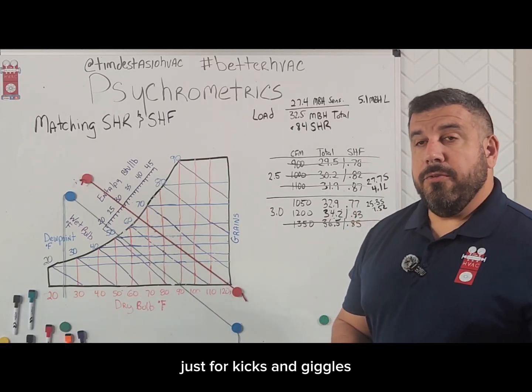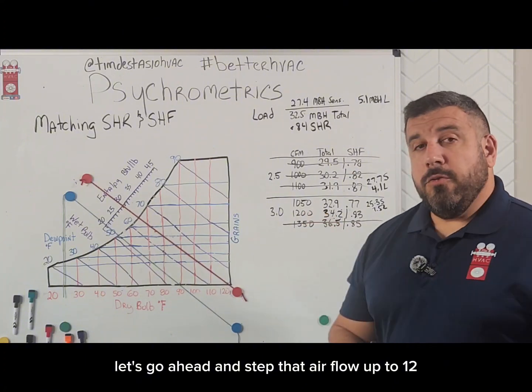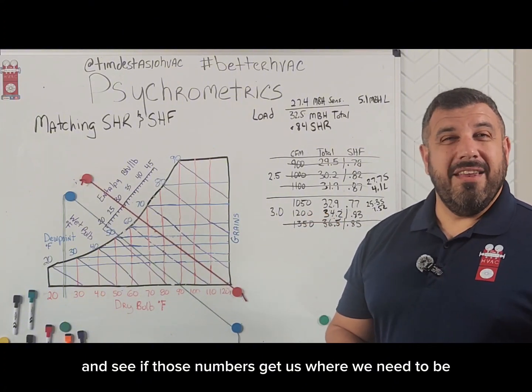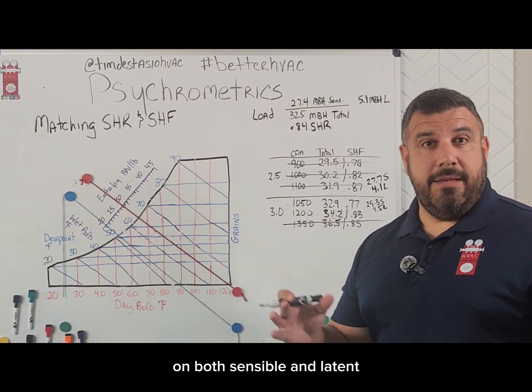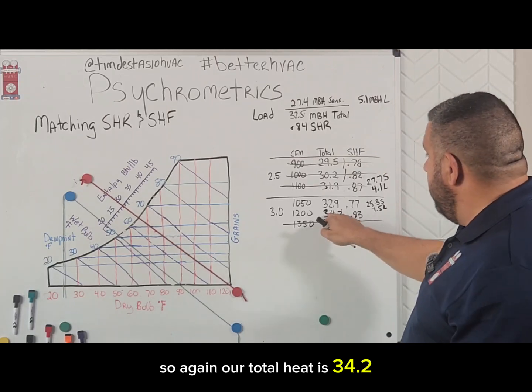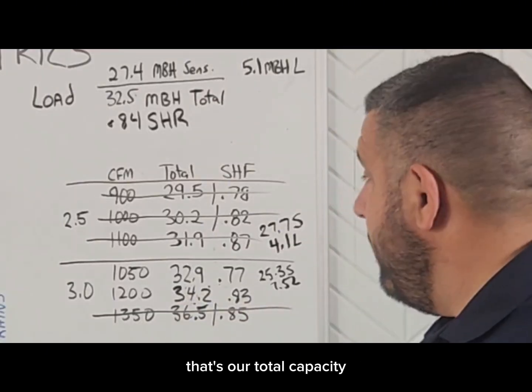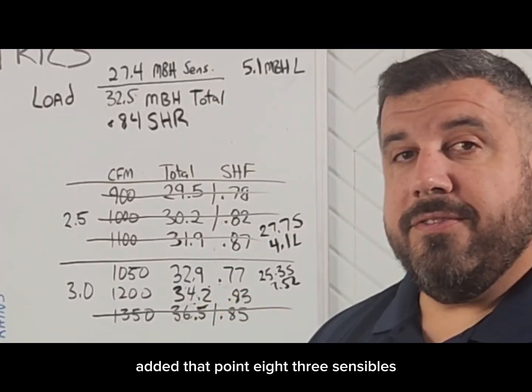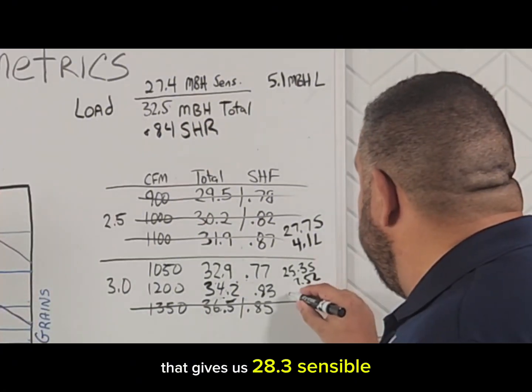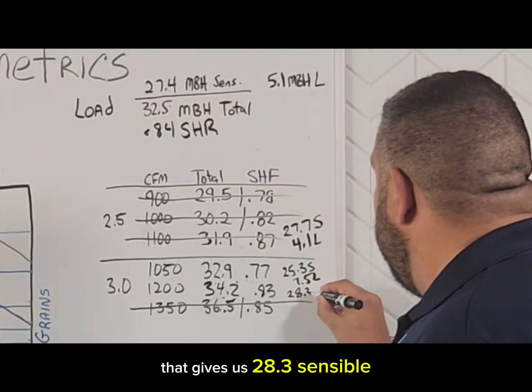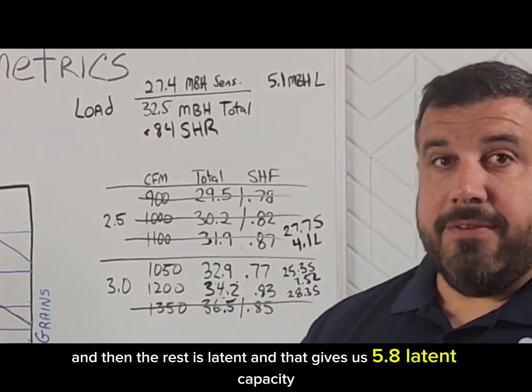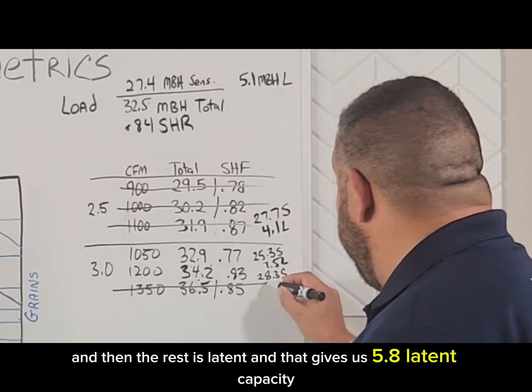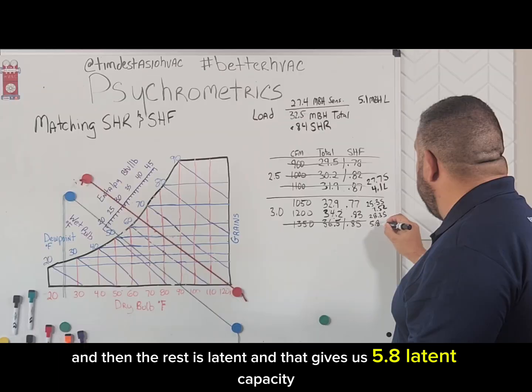Just for kicks and giggles, let's step that airflow up to 1200 and see if those numbers get us where we need to be on both sensible and latent. Again, our total heat is 34.2. That's our total capacity. Out of that, 0.83 is sensible. That gives us 28.3 sensible, and then the rest is latent. And that gives us 5.8 latent capacity.